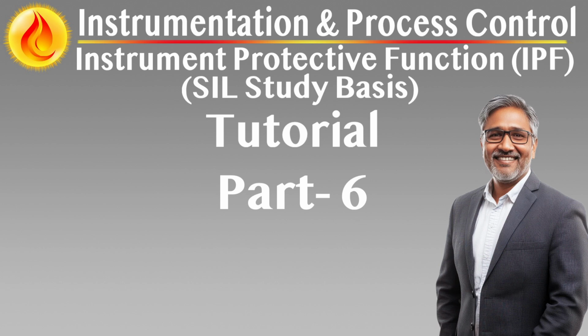Override history must be reviewed during periodic safety audits, proof test analysis, and performance reviews to assess patterns and potential design weaknesses. Post-override verification. Upon completion of maintenance, a full function check must be performed to confirm that the IPF has been returned to its fully operational state.